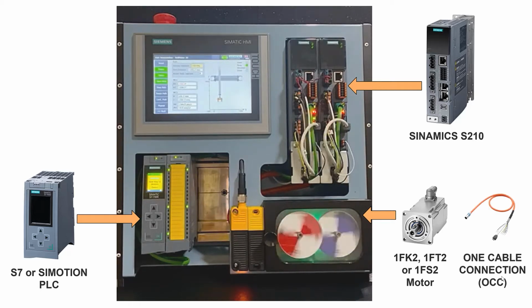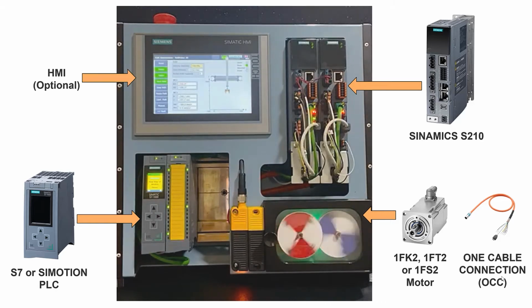They connect using only one space-saving cable for motor power, motor holding brake control, as well as encoder power and feedback. This one cable tells the S210 all the details on the motor, so there is never a need to manually enter motor data during commissioning. My demo unit also includes an HMI, which is optional for the S210 system.